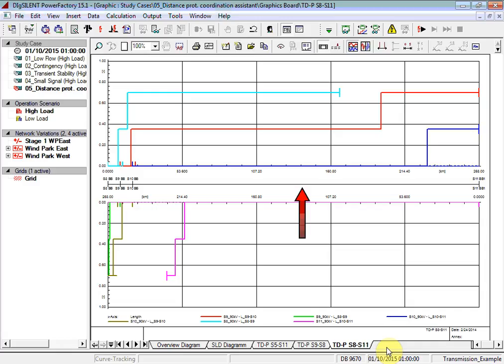Here, you can see that the relay installed at substation 10, located in the branch heading towards substation 11, will trip instantaneously. You can see that backup protection is also provided by the relays installed at substation 9, tripping time 350 milliseconds, and substation 8 with a tripping time of 700 milliseconds.